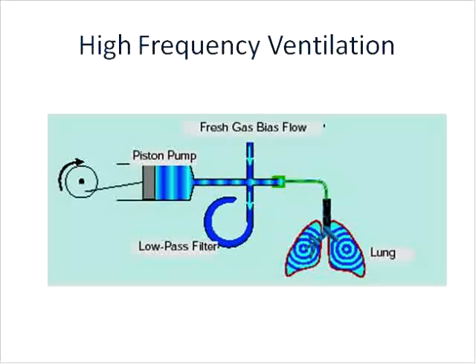Okay, high frequency ventilation, there are lots of them. At this point, high frequency oscillation is pretty much the one that gets used the most, and this kind of gives you that idea. So you have this piston moving back and forth and this fresh gas flow that not only adds to the tidal volume when the piston moves forward, but helps wash out CO2 when the piston moves backwards. And the low pass filter is, probably ought to come up with a better term.